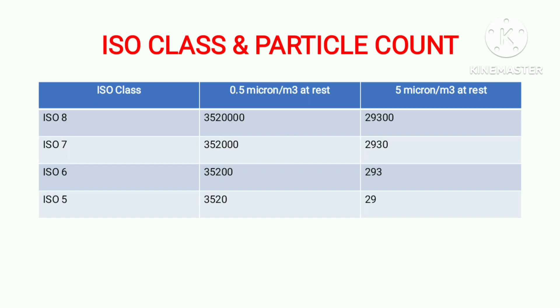Generally we have four ISO classes: ISO 8, ISO 7, ISO 6, and ISO 5. For ISO 8 class, the 0.5 micron particle count in one cubic meter volume at rest condition is 3,520,000, and the 5 micron particle count in one cubic meter volume at rest condition is 29,300.